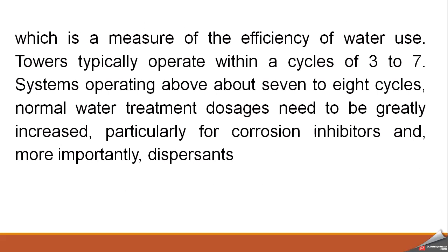So basically, COC is a measure of the efficiency of water use. Cooling towers typically operate within a cycle of 3 to 7, and previously I told you 3 to 10. So the 7 is basically taken as the value where we are trying to optimize the use of water and trying to avoid any of the effects due to concentration of the solids inside the water, which may be scaling or corrosion or other effects.